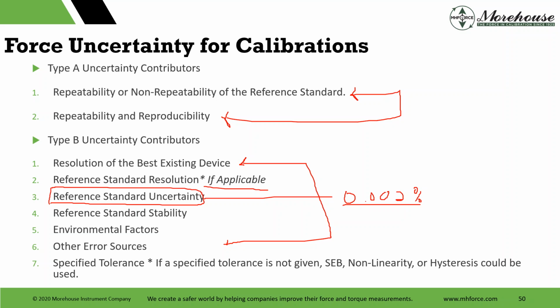Reference standard stability, environmental factors, other error sources, specific. And when we look at stability, we're looking at drift. I mentioned that earlier. If you're claiming your device is good to 0.01% of full scale, whatever it is, say that's your spec, and it goes out to the lab and the lab constantly fails it, that's the time that says, hey, you don't have that. Stability is greater than your perceived accuracy statement, and therefore you should shorten the cal interval or raise your stability.